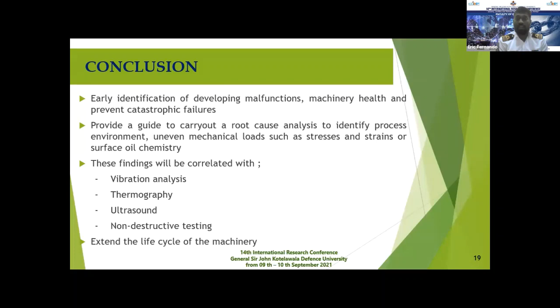In order to find the exact root causes, we are correlating all these test records with the vibration analysis results, the thermography results, the ultrasound results, and the non-destructive testing results. So it is confirmed that this type of continuous monitoring of the wear down of the engines fitted in SLN major vessels will give us an opportunity to extend the life cycle of the machinery as well. So these are the references.